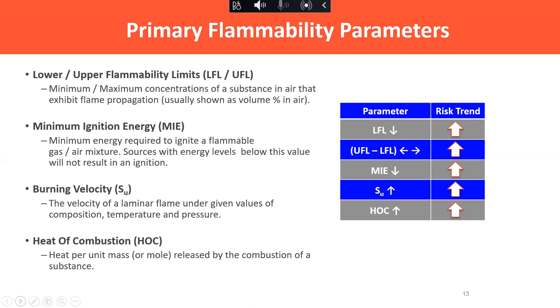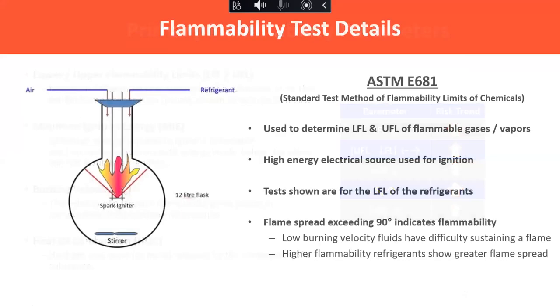If we go on to the next chart, this is basically the standard ASTM method for determining flammability. It's basically a flask, and it starts out filled with air, and you add a refrigerant to it that you think might be flammable. Once it's filled with a known composition, you ignite a spark and see if you get flame extension, or if you get this stuff to burn. If not, you go into a little more and work your way through it.